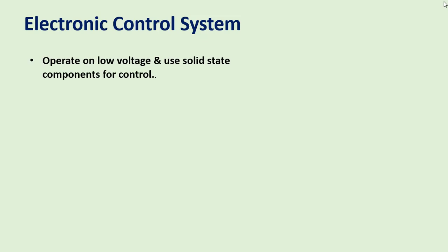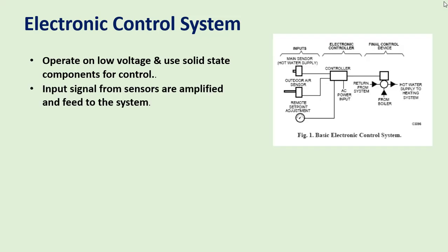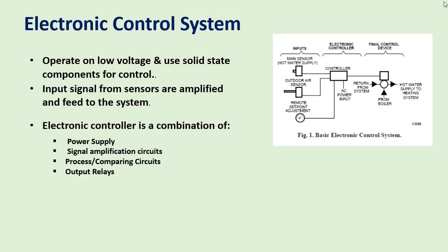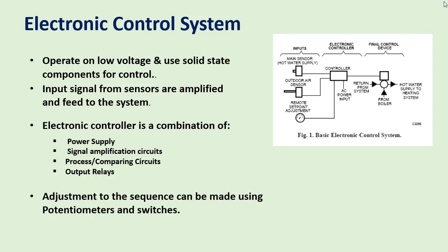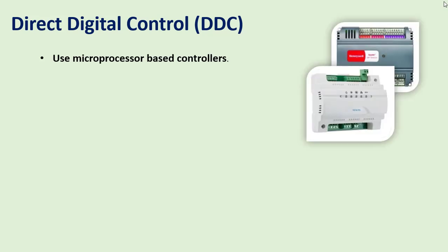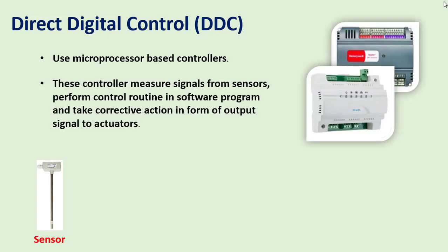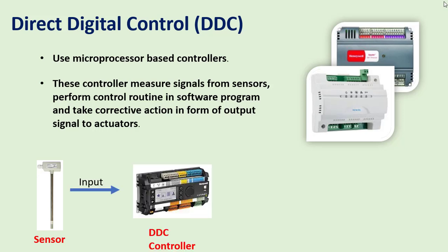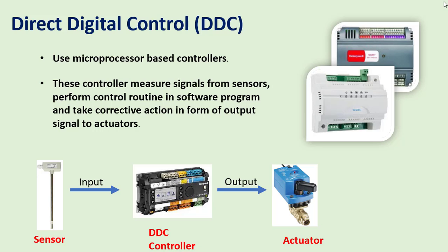An electronic control system operates on low voltage and uses solid-state components for control. Input signals from sensors are amplified and fed to the system. An electronic controller is a combination of power supply, signal amplification circuits, process comparing circuits, and output relays. Adjustments to the control sequence can be made using potentiometers and switches. Direct digital controls, or DDC, use microprocessor-based controllers that measure signals from sensors and perform control routines in a software program.